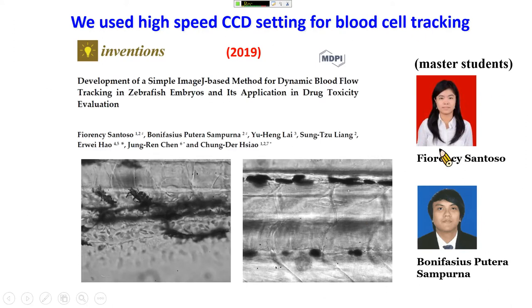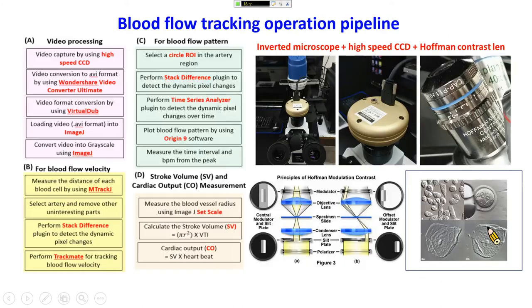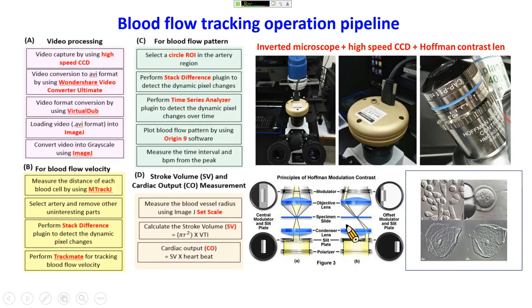This work was done by my students Phil and Bonnie. The setup uses an inverted microscope with a high-speed CCD, and a Hoffman modulation contrast lens to enhance image contrast. The Hoffman modulation lens blocks the light path on one side while opening the other, making the image appear more three-dimensional and enhancing contrast without needing to stain the zebrafish embryo.